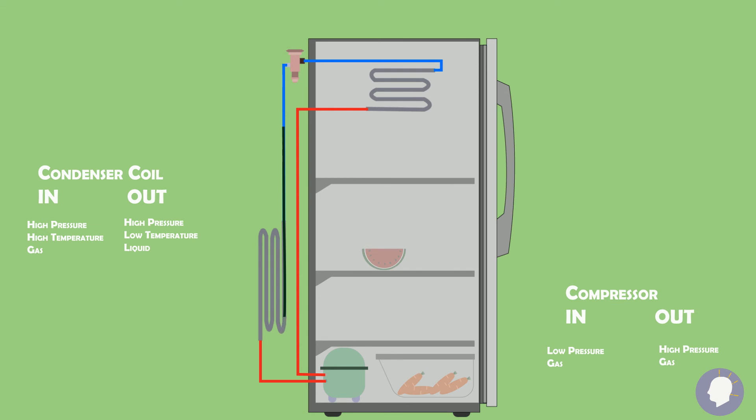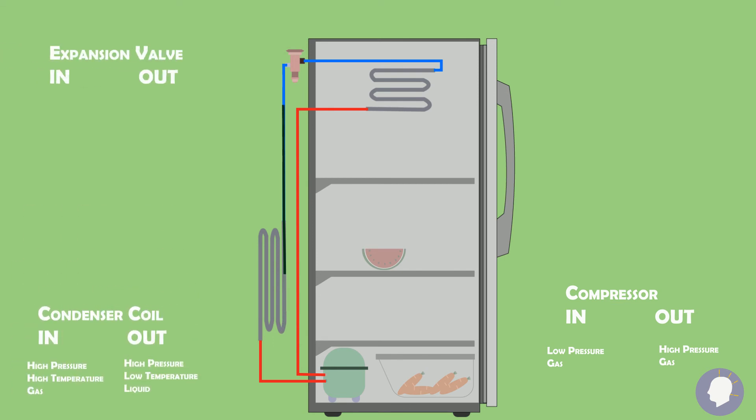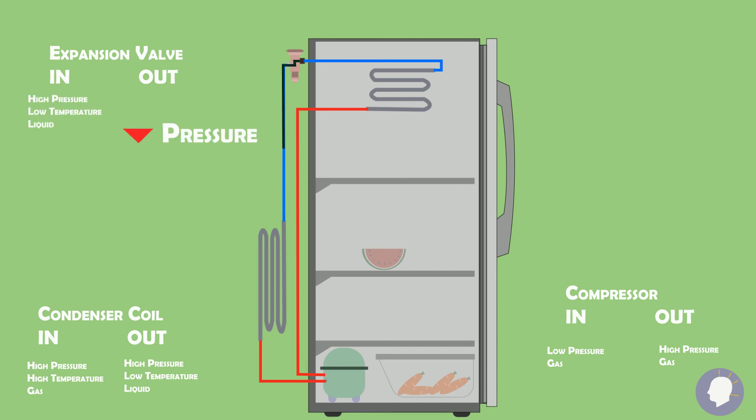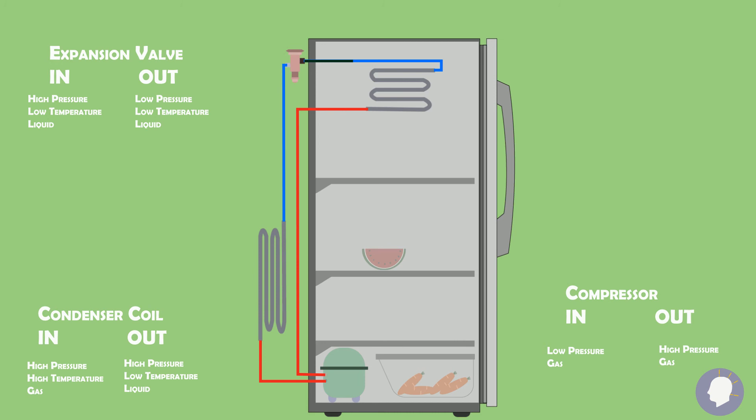The fluid which is now a liquid makes its way towards the expansion valve, which it enters as a high pressure liquid. The expansion valve expands the liquid which causes a sudden drop in pressure. Now, the fluid leaves the expansion valve as a low pressure, low temperature liquid and makes its way towards the evaporator coil.